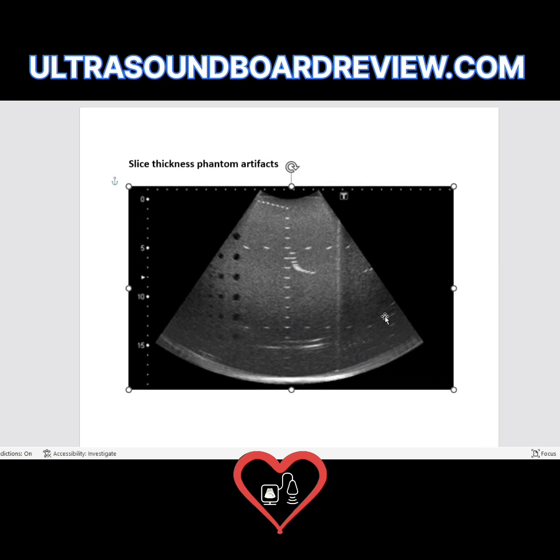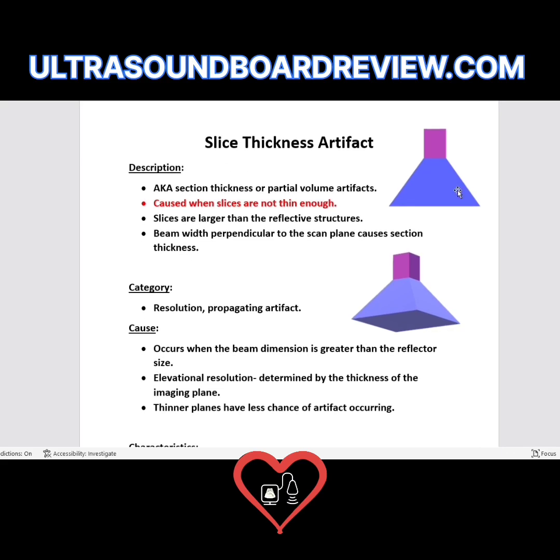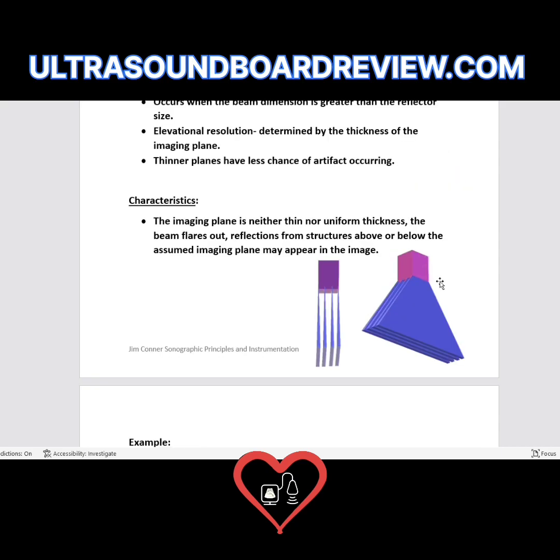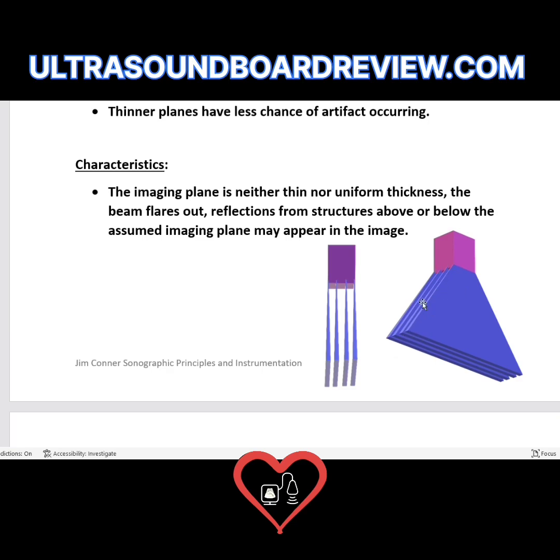Then we have the slice thickness phantom. With ultrasound we see a sector in a 2D imaging plane, but the ultrasound is actually transmitting a beam that has a 3D volume to it — it has a lot more volume than what we see. There are actual slices that come out at an angle. If these slices aren't razor thin, you're going to start getting slice thickness artifacts. For your boards, remember that partial volume artifacts is the same as slice thickness artifacts.